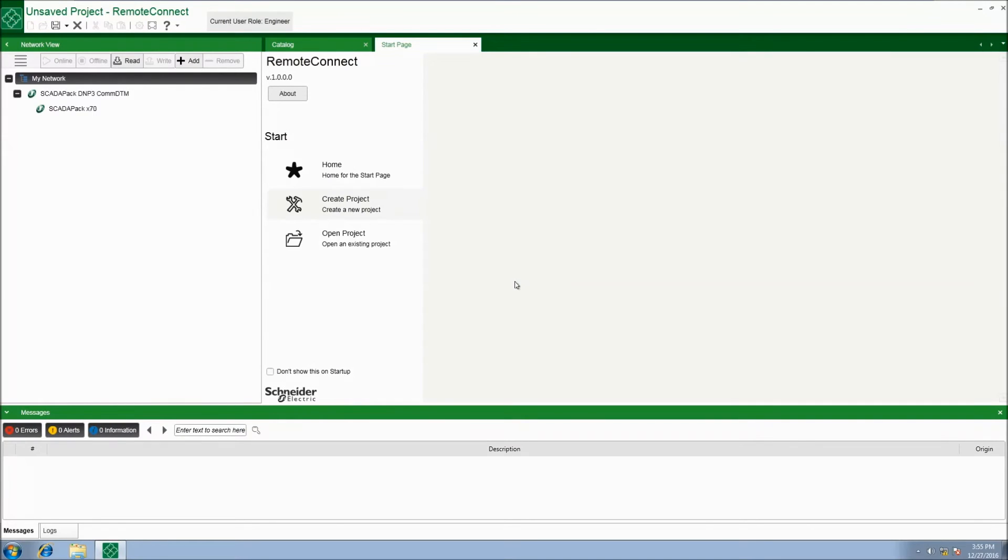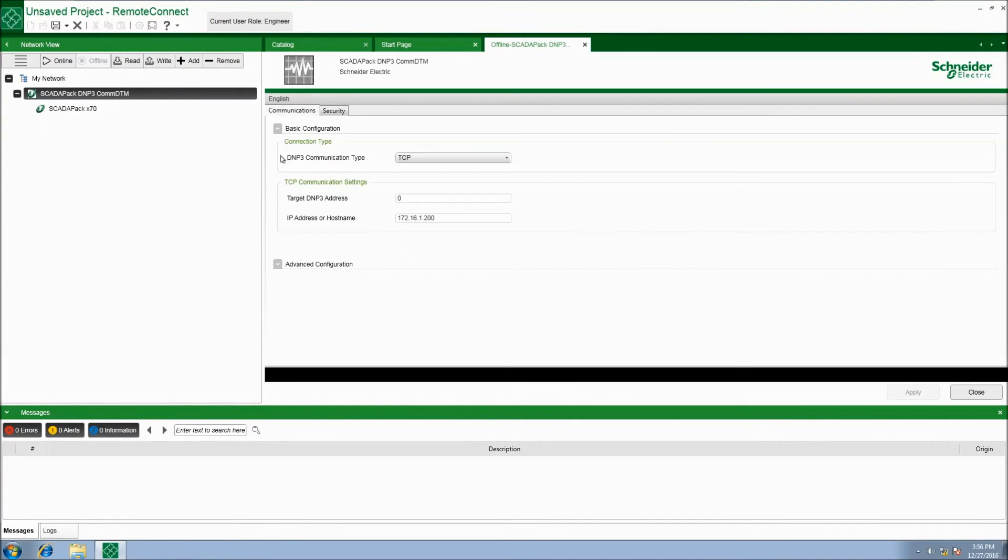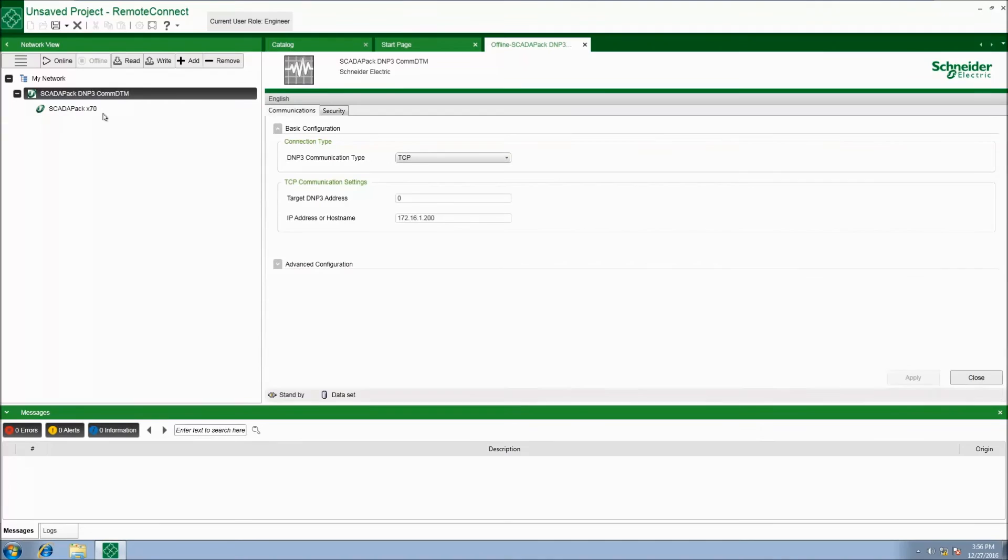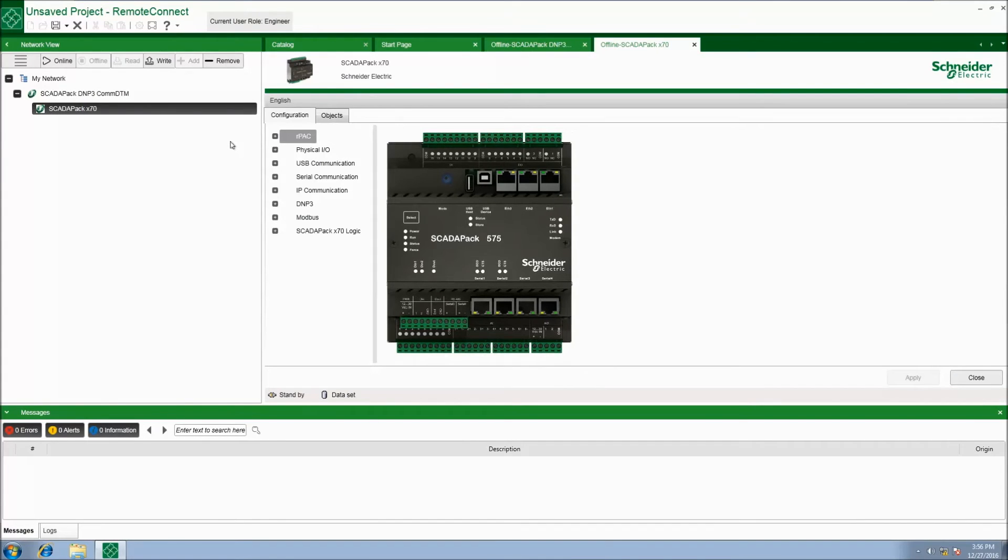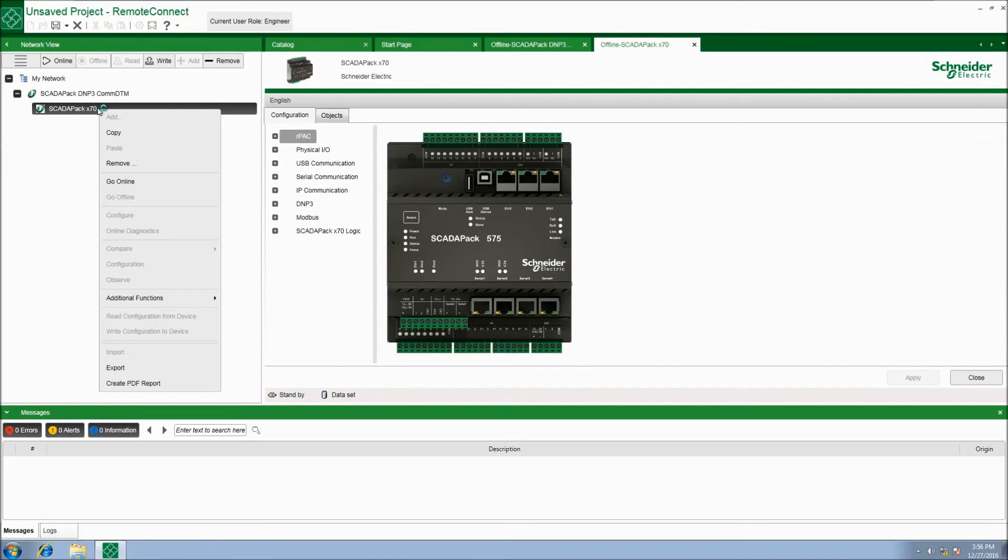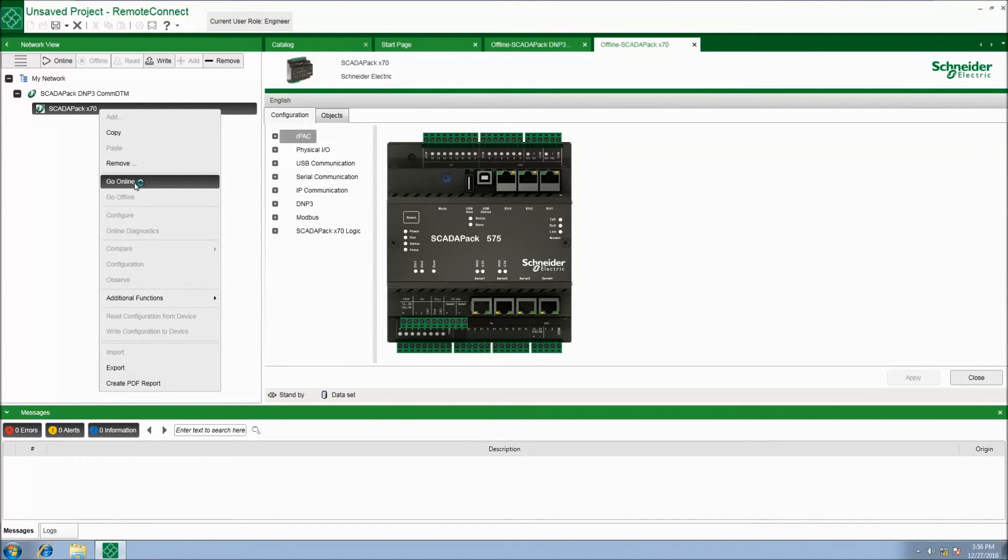Double click on the SCADA pack DNP3 COM DTM to display offline configuration mode to check the IP address. Double click on the SCADA pack X70 to access offline configuration. Now we need to go online with the SCADA pack X70. To do this, right click on the SCADA pack X70 object and select go online.